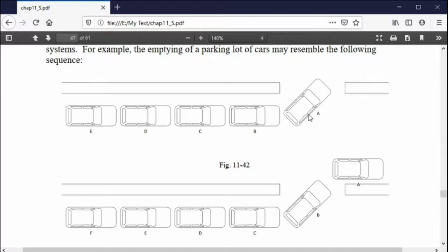I looked at it and I said, well, if you initialize with another car in this position, in other words, two cars in this position instead of one, everything from that point on would just work. And I tried it and it worked. I went and asked the electricians, have you ever seen this thing work that way? And he said, oh yeah, every once in a while it skips and gets into that mode on its own.